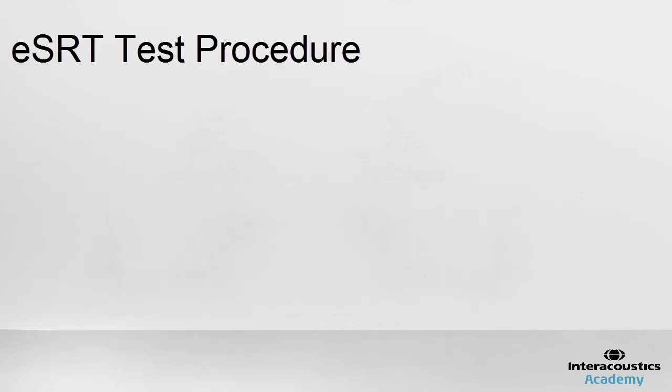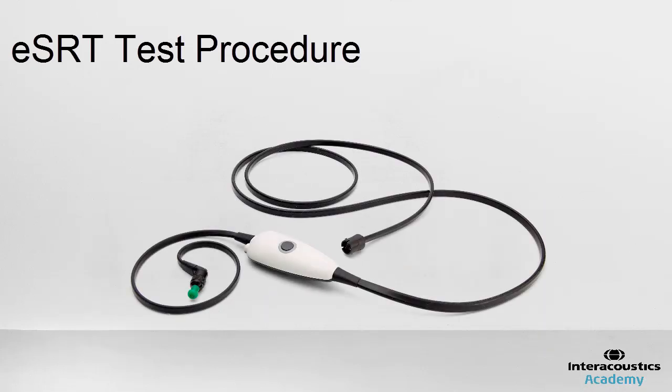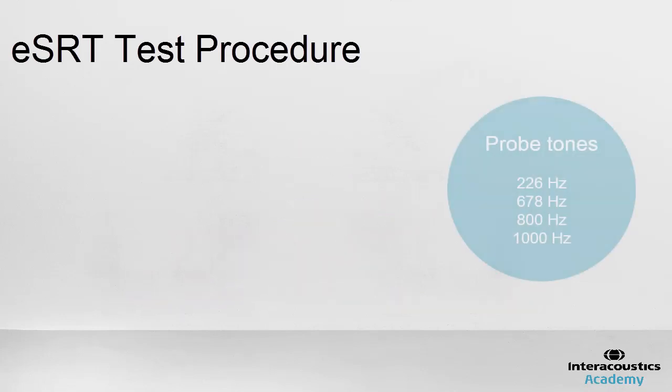A good probe fit is essential in recording the ESRT, and therefore it is recommended to perform the test using a clinical probe. A probe tone is presented through the probe in order to detect when a reflex is present. The probe tone used can be set to 226Hz, 678Hz, 800Hz, and 1000Hz.